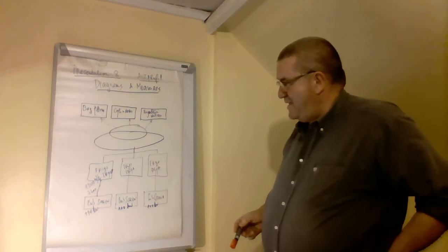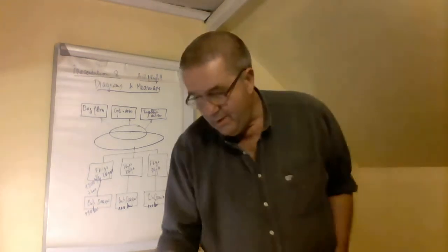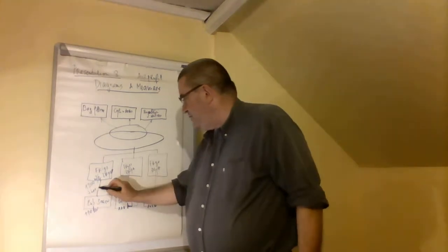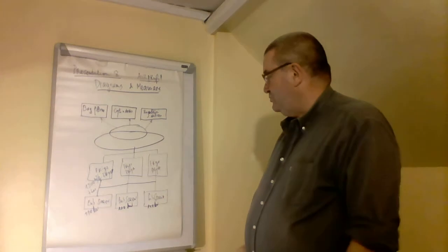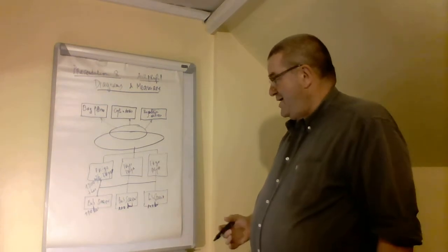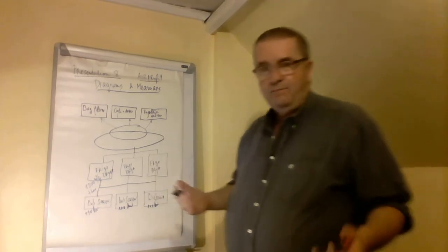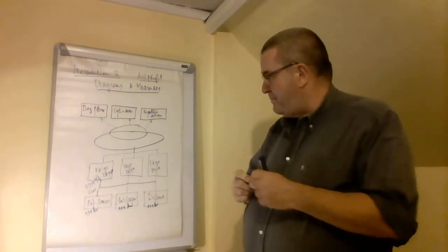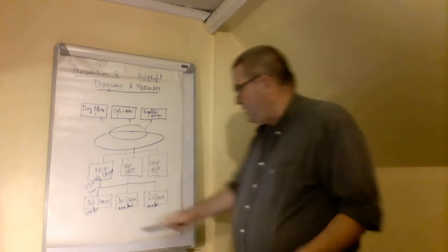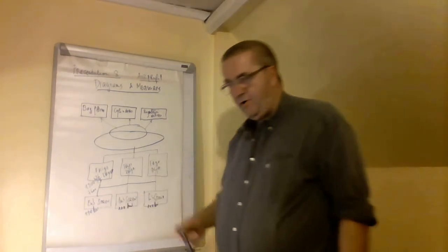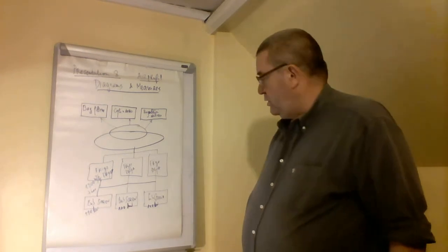It means that compared to a diagram where you would have here a collector, and maybe 1 or 2 or 3 dryers, you may have lower availability. So the probability that you have no good solutions because one compressor and one dryer are out of work, which happens about 2% of the time in a normal installation.